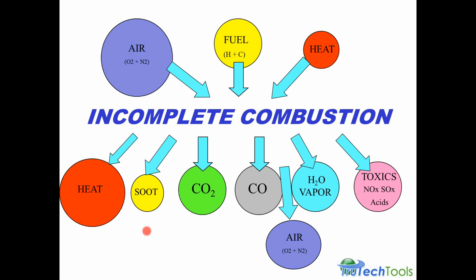An oil or smoke spot tester on oil systems can measure the soot. A CO sensor in the combustion analyzer measures the CO. An oxygen sensor measures the oxygen present. And there are some analyzers that alternately measure the CO2 present instead of the oxygen. And we'll show you about the relationship between those two in a minute. The nitric oxide gas here is one we'll be talking about in particular because that one can interfere with the correct measurement of CO.